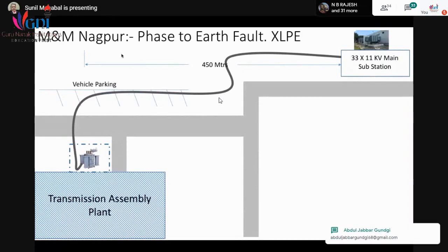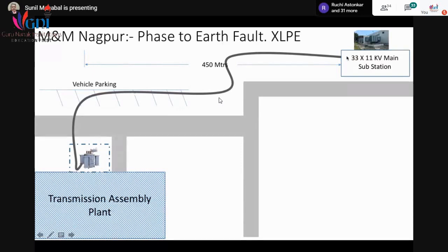So the distance between this substation and the plant was 450 meters. We had installed the RMU and we wanted to charge the cable which was already laid underground 2 years ago. We did it on Sunday afternoon, and then in the evening we wanted to charge it. As soon as we charged it, it punctured and developed an earth fault. It was already 6 p.m. in the evening, and next day the production was to start at 7. So we had very little time left, and there was a fault.